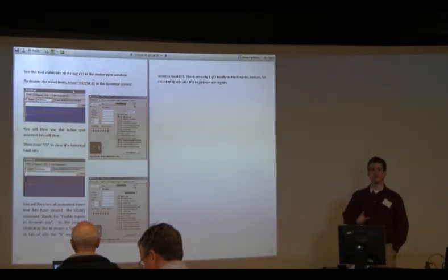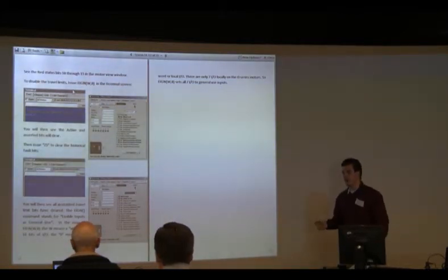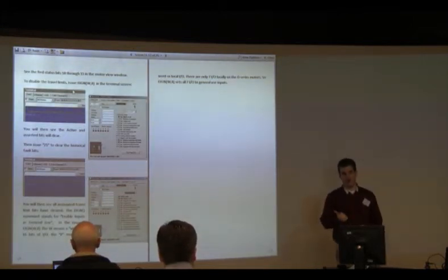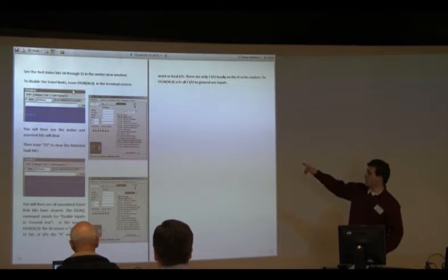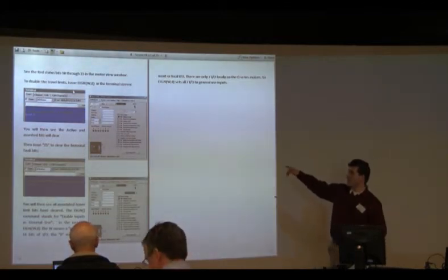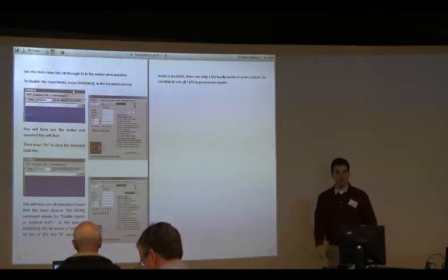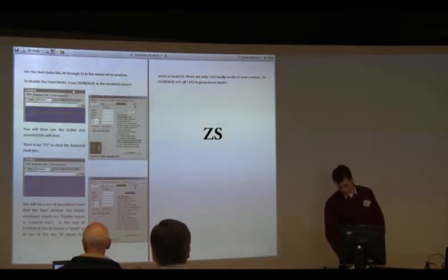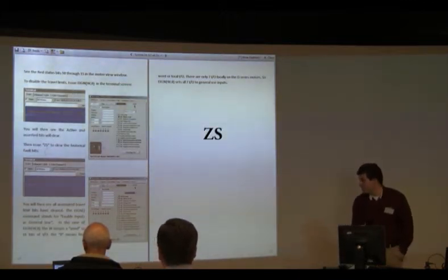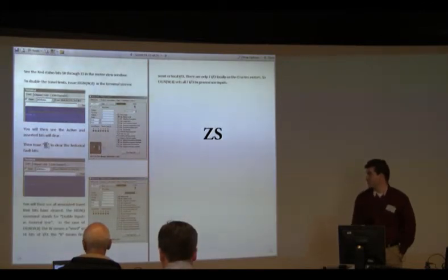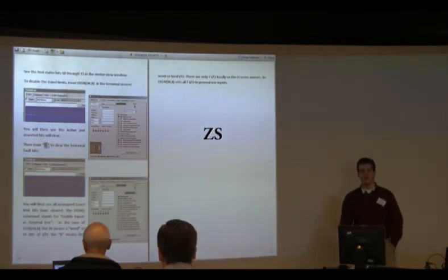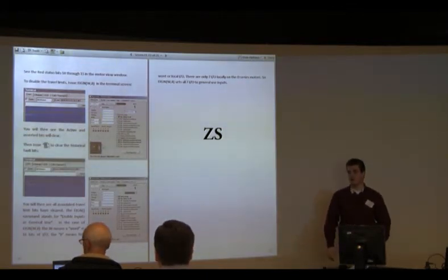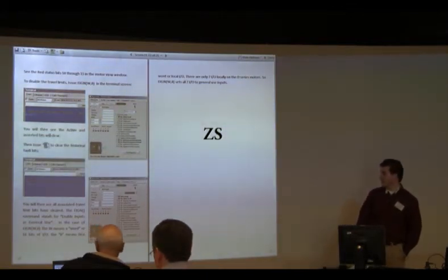But it knows something went wrong before. It says, wait a minute, I know that a minute ago you were hitting my limits. Something went haywire. So you have a historical hardware limit bit that is set. So that needs to get reset too. So you're going to issue a capital Z, capital S, as in Zebra Sam, just like it says right here. And that'll clear the historical fault bits. And ZS is sort of a general command to clear errors that are historical in the motor. Should clear everything.